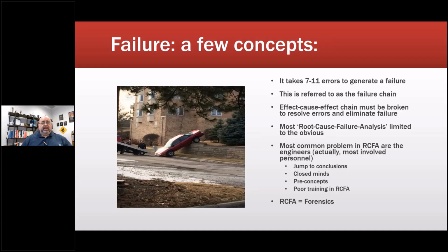There is not a project that we have been brought into that we have not solved. Last Monday, we were called to take a look because there was a huge issue with an energy project at a hospital. I walked in there, and in 15 minutes we figured out what had been wrong for months. They forgot to make sure that the electricians connected the systems properly, and they had not. Basically, they'd put in filters and shorted the filters to themselves, so there was zero impact on that process. Now we're into a project where we have to go back and fix all of it. But they were trying to tell us, oh no, it's this, oh no, it's that, or oh no, the project didn't actually work, when it just wasn't installed correctly. So these are things you have to keep in mind and keep an open eye on.